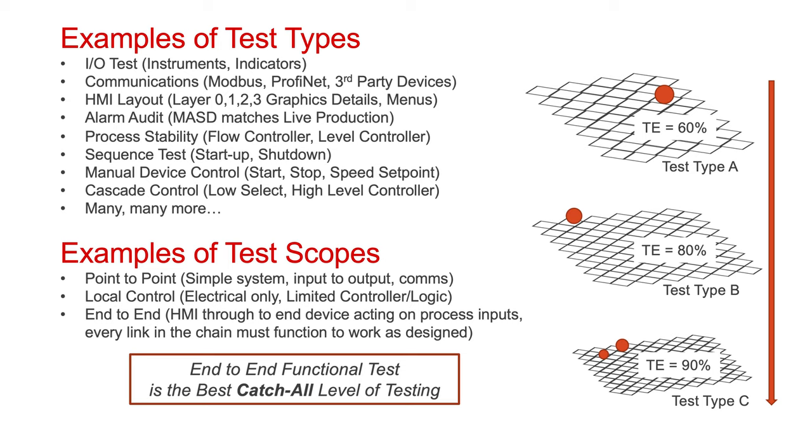Process stability is another example, for flow controllers and level controllers. Sequence tests are another example, whereby we have a startup sequence and a shutdown sequence, ensuring it starts up and shuts down through all the different combinations, and that the interlocks from step to step work correctly. There's also manual device controls — putting a device into manual and ensuring that it starts and stops, or if it's a variable speed or variable position device, that it proceeds to the set position or set speed. Cascade control tests, for example low select and high select, if there are multiple cascaded controllers fed into a controlled device, making sure that the low select is selecting correctly. But that's just a short list — there are many more.